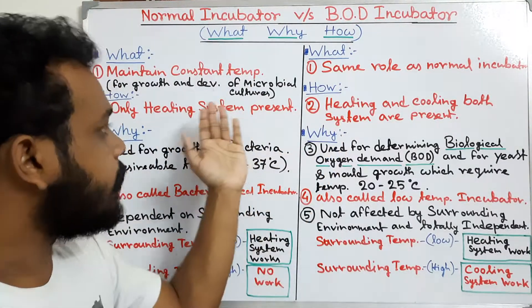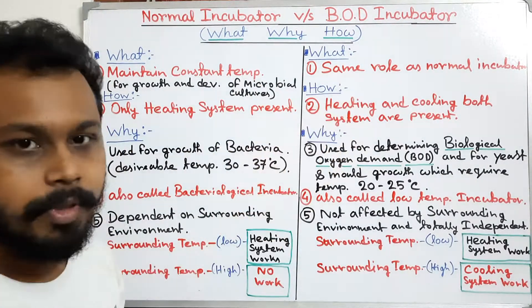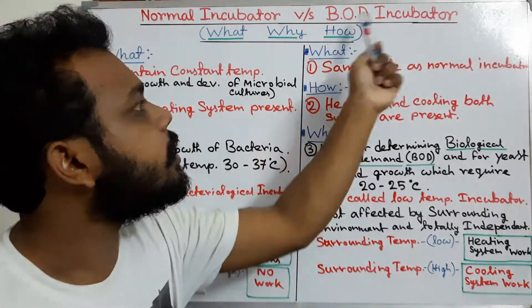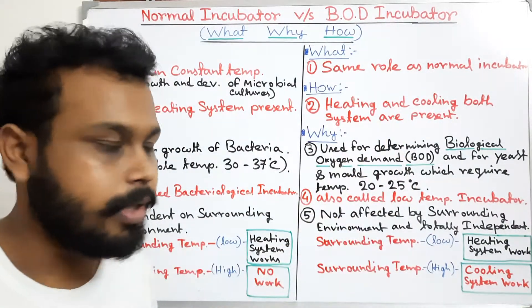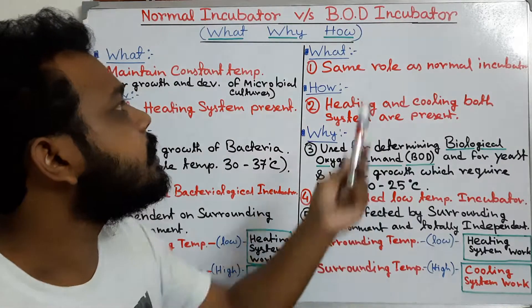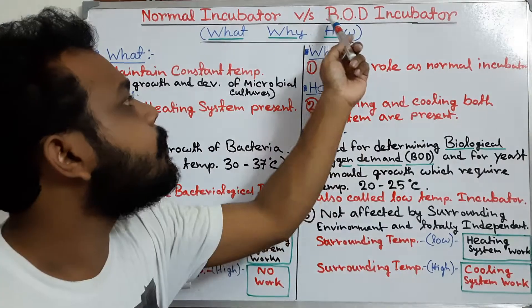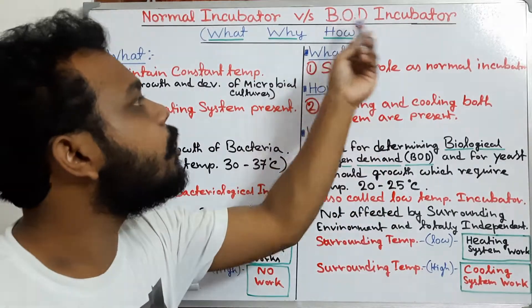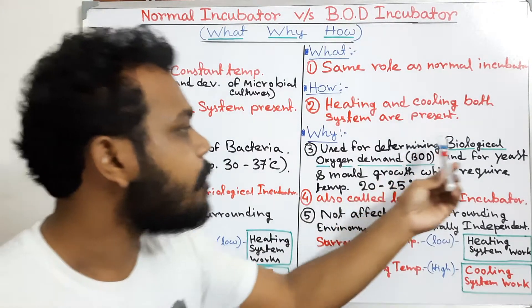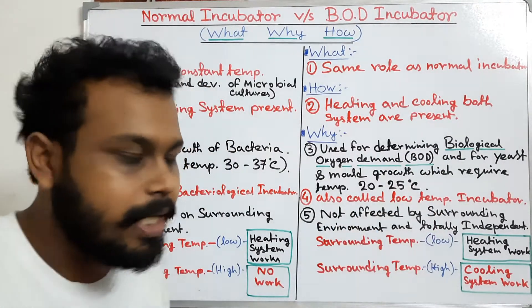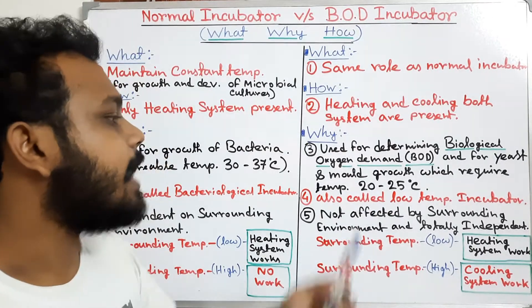That's why the BOD incubator is also known as the cooling incubator. But then why is it called BOD incubator instead of cooling incubator? BOD means Biological Oxygen Demand, and for biological oxygen demand determination we need a temperature of 20–25°C.